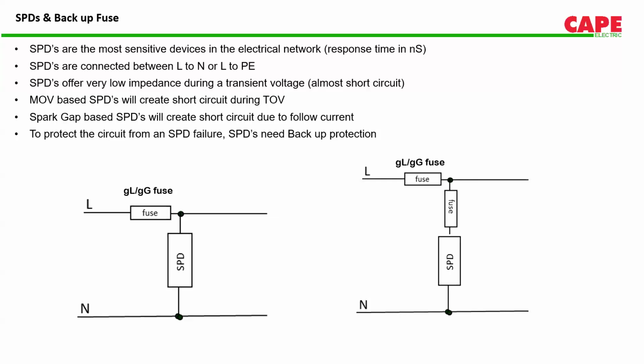This SPD fails. Once it fails, there are two possibilities. It can fail in a short circuit mode or it can fail in an open circuit mode. Once it fails in an open circuit mode, that means the thermal disconnector inside the SPD disconnects, it becomes an open circuit mode of failure and there is no problem. SPD disconnects itself.